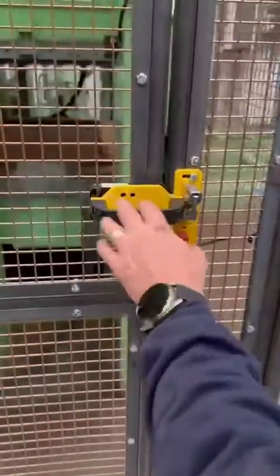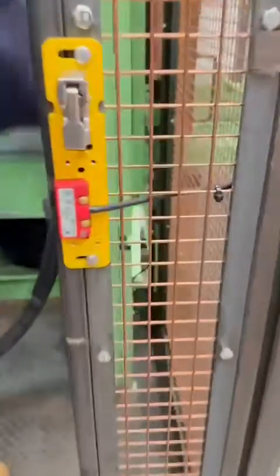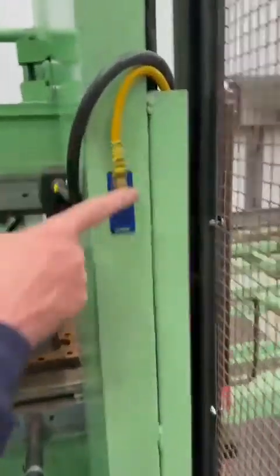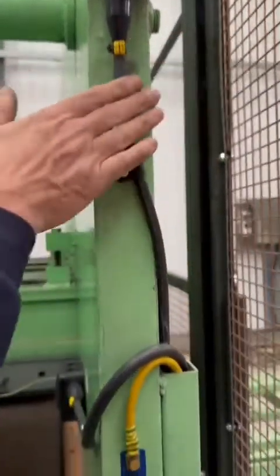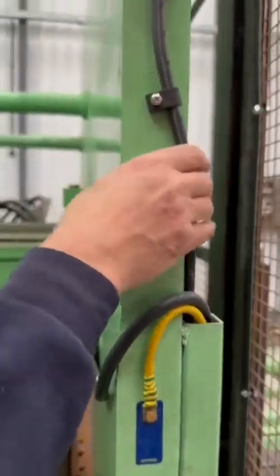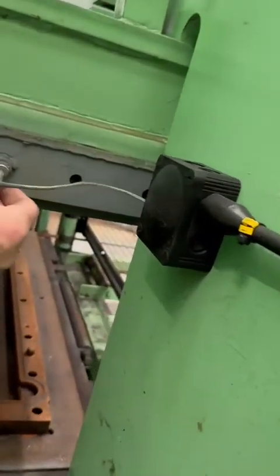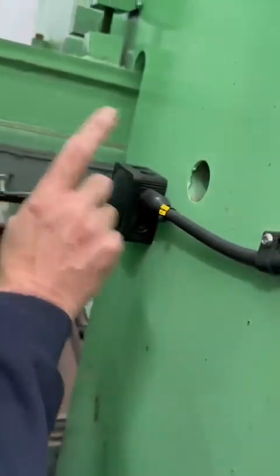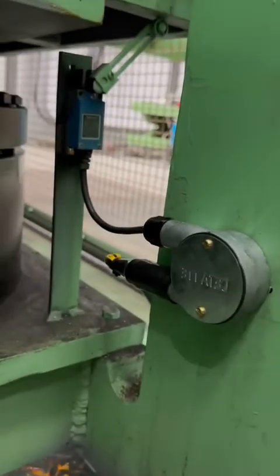So as we go into the machine, we've now got a gate interlock on there, so that would shut the machine down should anyone go in. We've got a new earth bond onto here. We changed the beacon, got rid of the little 2-core flex. It's 240 volt, so that's got a proper armoured on now. The heat probe here has now got a proper junction box, armoured cable, a lot neater.